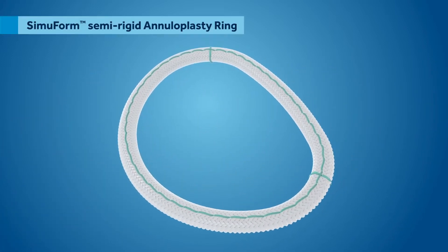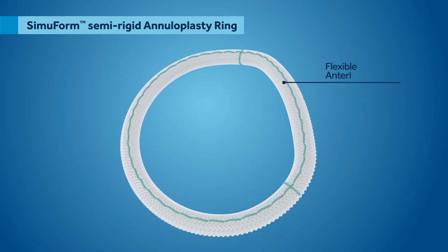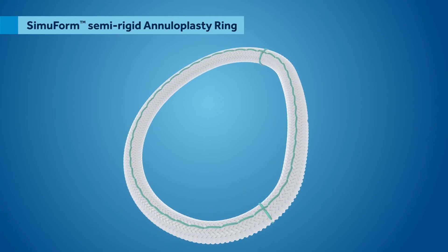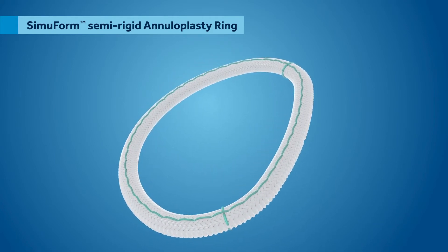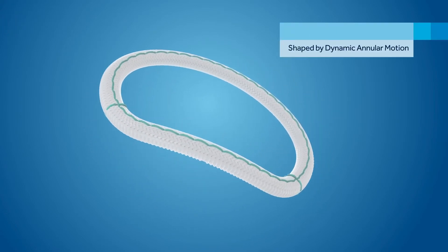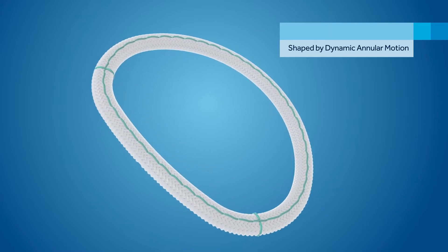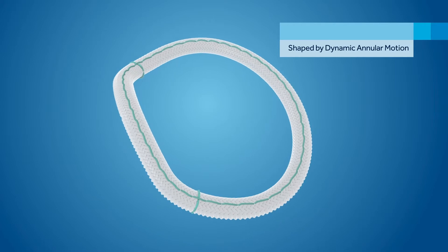The SimuForm Semi-Rigid Ring combines semi-rigidity for posterior remodelling with a flexible anterior segment, allowing for the physiologic motion of the aortic mitral curtain during the cardiac cycle. This distinctive design, along with the smooth braided polyester material, enables the SimuForm Semi-Rigid Ring to take a saddle shape in systole and flatten to a planar shape in diastole.